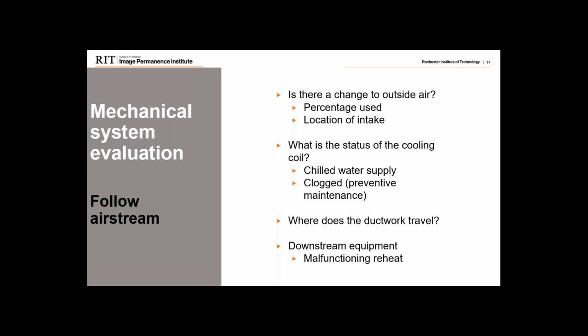Location of the intake, where that could be. In my own experience as a facility manager years ago, the outside air intake for a medical facility was by the loading dock, and there were two problems with that. First, anytime a vehicle pulled up to unload and sat idle, the outside air was pulling in exhaust from vehicles, so it was no longer fresh air. We now had some polluted combustion from vehicles, and it was also the smoker's door, so when smokers would go outside, people within the facility could smell their cigarettes. We wound up having to move that. So keep in mind, the location of the intake could play a major factor.